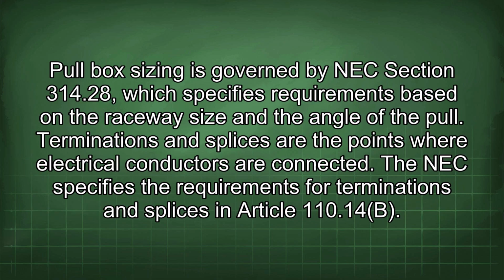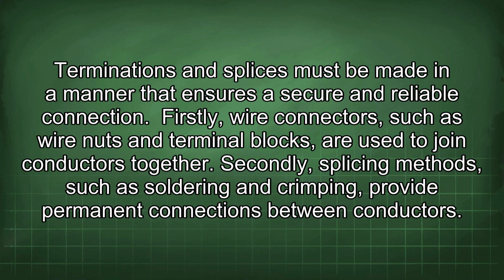Pull box sizing is governed by NEC Section 314.28, which specifies requirements based on the raceway size and the angle of the pull. Terminations and splices are the points where electrical conductors are connected. The NEC specifies the requirements for terminations and splices in Article 110.14(B). Terminations and splices must be made in a manner that ensures a secure and reliable connection.